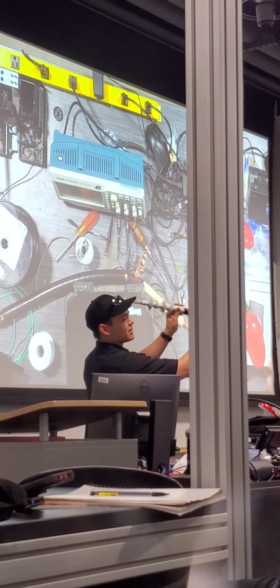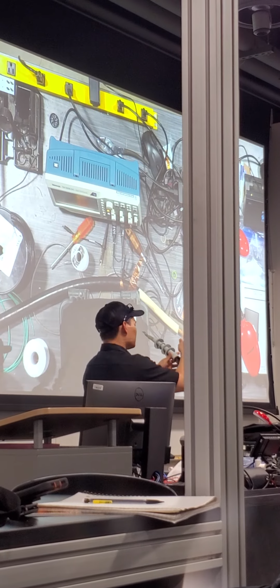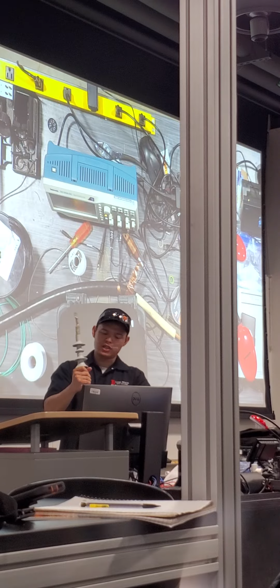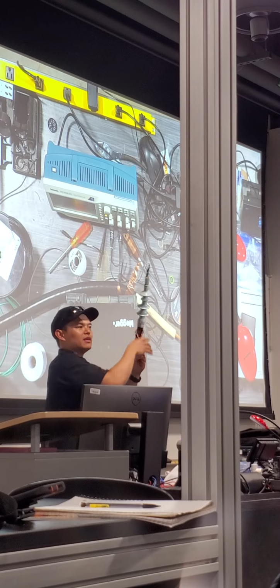So as we're seeing, eventually, like the tape shield, you'll see examples of this, but at the end of each cable you'll see that all of these individual strands actually tie together. They're all braided together. So by the time you clamp onto one of these, you're testing them all. So a fault anywhere in the cable, ideally, should be detected when you test it at the end of the cable. So let's do just that.